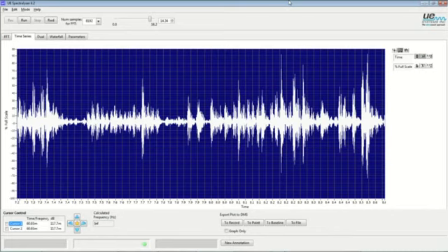But I base criticality and develop action plans dependent upon how frequent the discharges are. The more frequent they become, the greater the criticality in getting it changed. But when you identify a tracking event, there should be an action plan put together immediately based on the analysis to deal with the equipment and address it on our terms, as opposed to allowing a failure to occur and have the equipment dictate the terms.